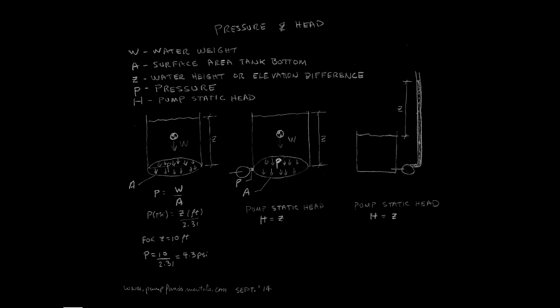No pump can run without being connected to a suction tank, and that being the case, there is a certain amount of pressure energy given to the pump via the pressure in the suction line. We need to subtract that contribution of energy from that at the pump discharge to describe what the pump is providing on its own. Therefore, the pump head will be the difference in level produced by the pump discharge versus what's provided to the pump suction via the suction tank level. The pump head will be Z, and if Z is 10 feet, the pump head is 10 feet.